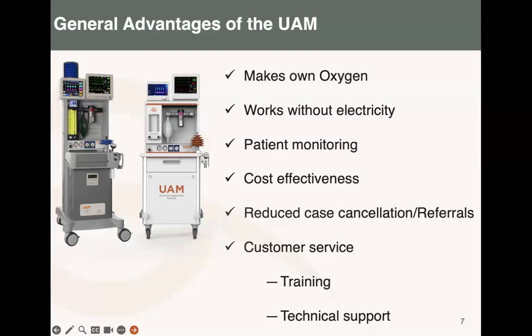Yes, of course, it can work without power, but when there's no power, the concentrator will not be functioning. That's why we advise you to have the concentrator and the cylinder, but at least you will still continue with the surgery, because the ventilator will still work because it has a battery. The monitor will still work because it has a battery, and the oxygen monitor will also continue working because it also has a battery. So the patient monitoring is also part of the machine. It comes with the patient monitor.